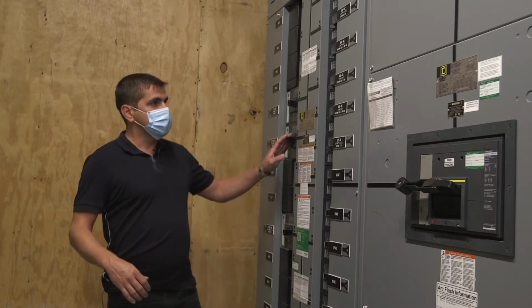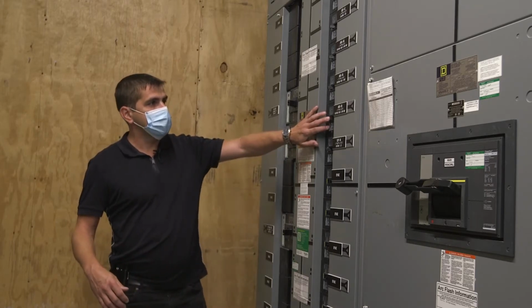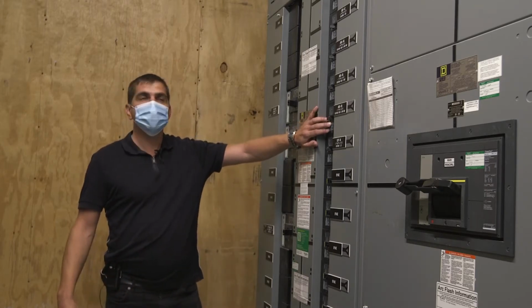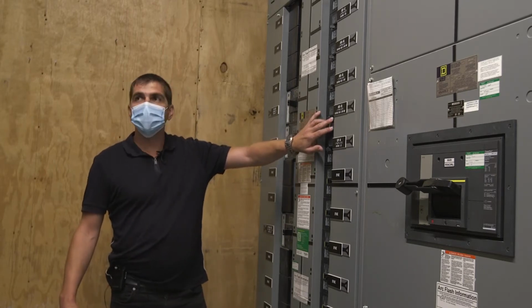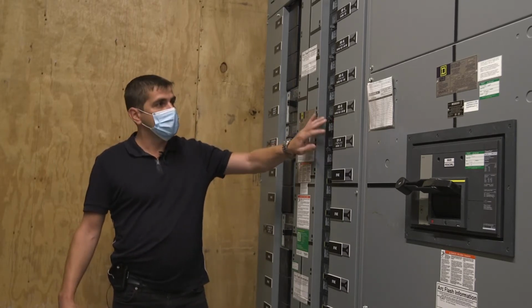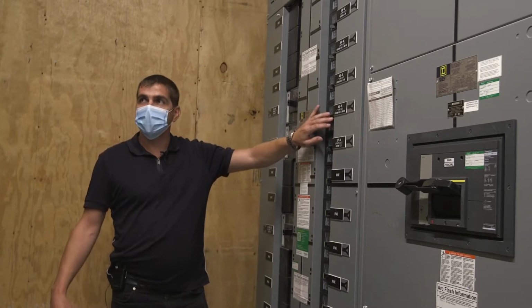All of the circuit breakers are in the left position when they are on. In case the breaker trips, it's going to be in the middle position. In order to reset it, you would have to turn it off completely and then turn it on again.